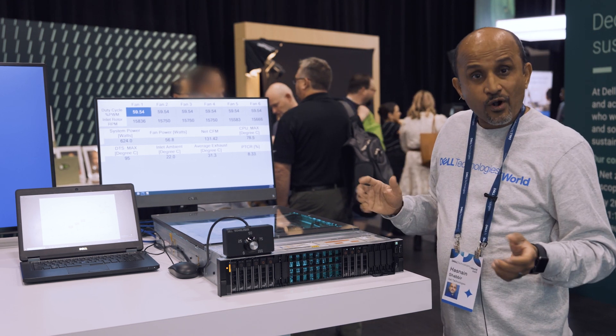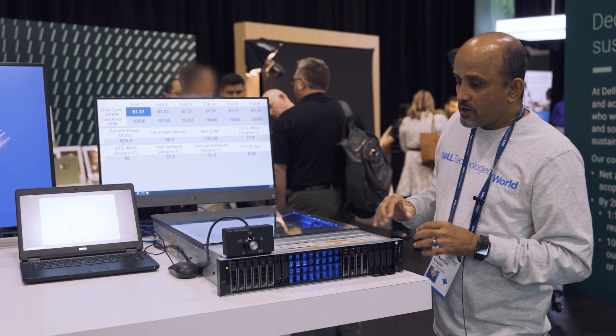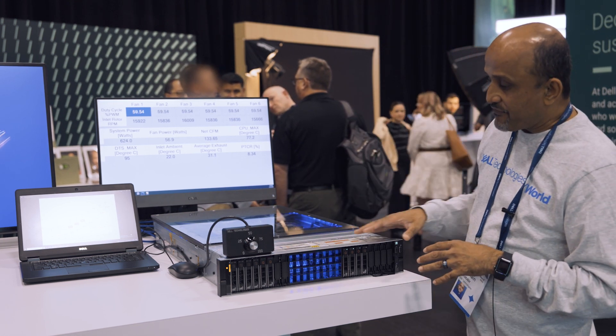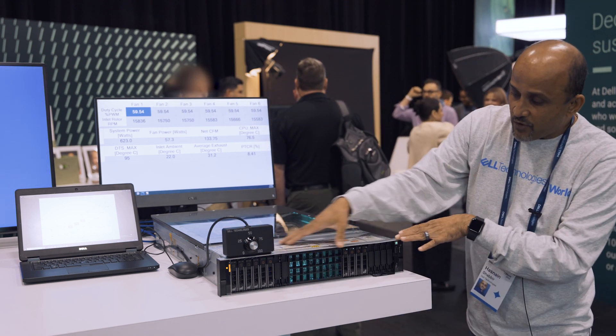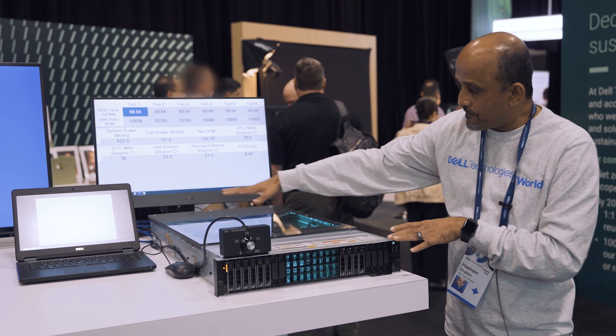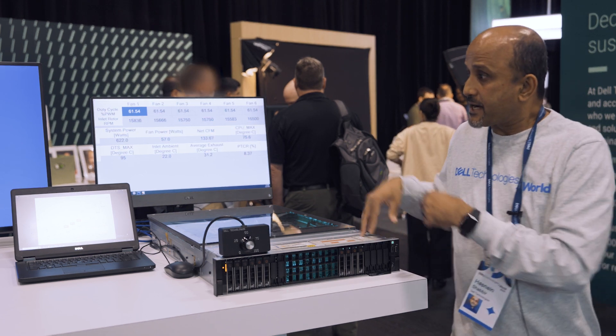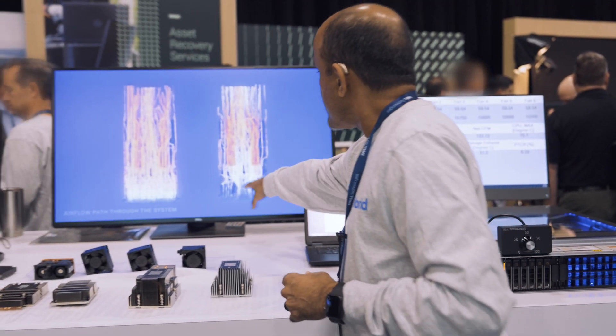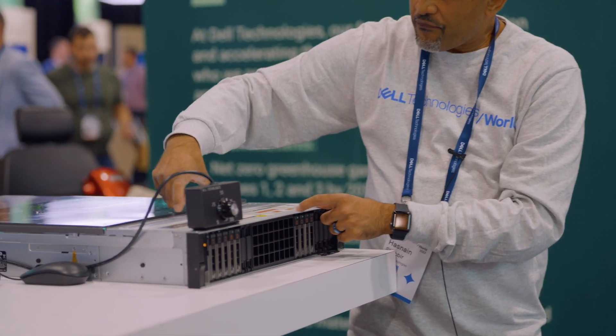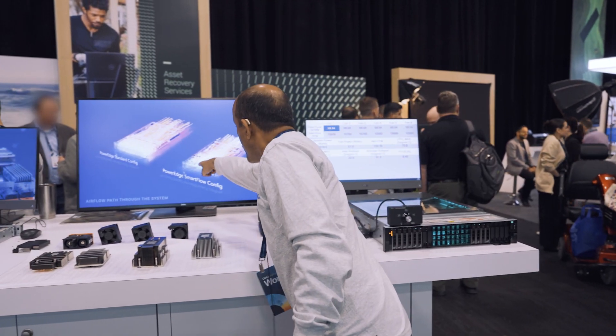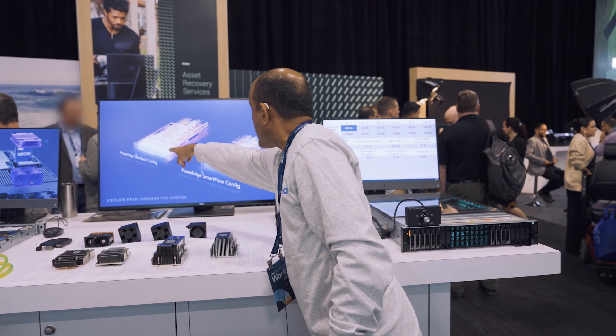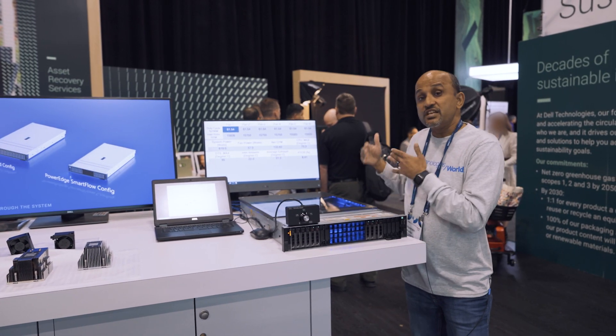What I just explained is all about fan control and fan power optimization. Now let's talk about how we optimize airflow in the box. This animation gives you an idea that we have what we call a smart flow config, meaning this system has been optimized for airflow compared to a standard config. By breaking the back plane into two parts, we have created an exclusive airflow channel that allows significant airflow from the middle.